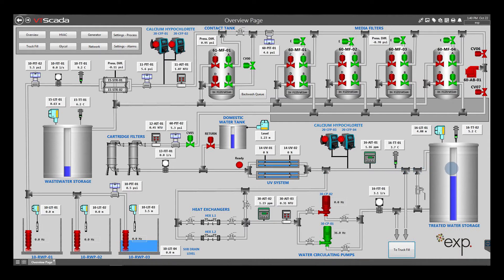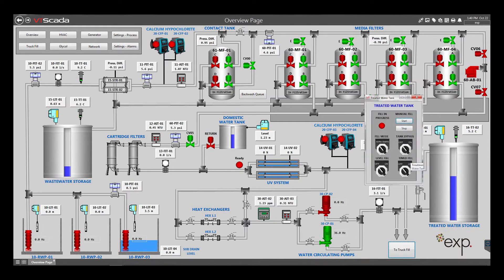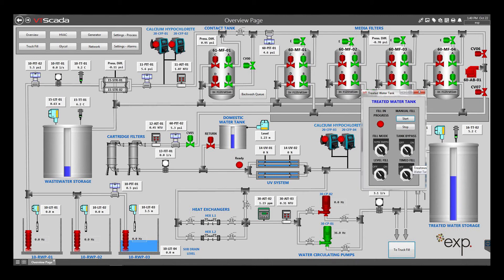The treated water tank pop-up has important controls. It will indicate if a fill is in progress. The manual fill start and stop buttons allow the operator to manually start or stop a tank fill. The fill selector switch allows the operator to select the rate the treated water tank is filled. In normal position, the system will use one raw water pump to fill the tank. In the emergency position, two raw water pumps will fill the tank.